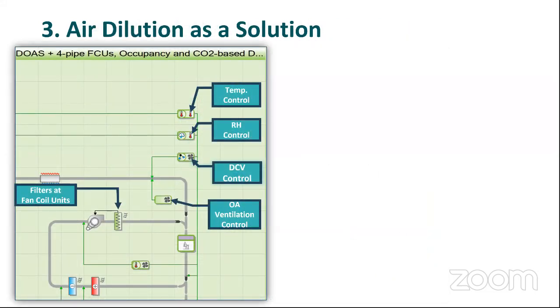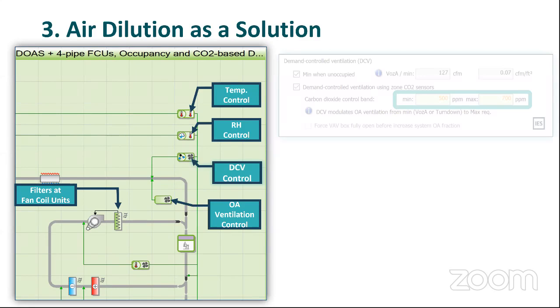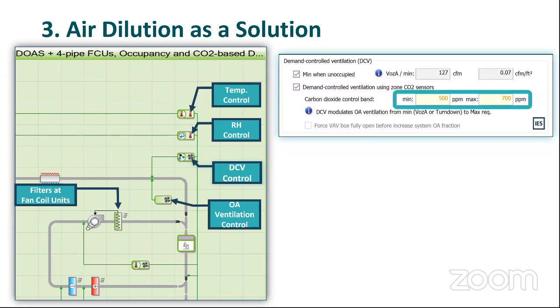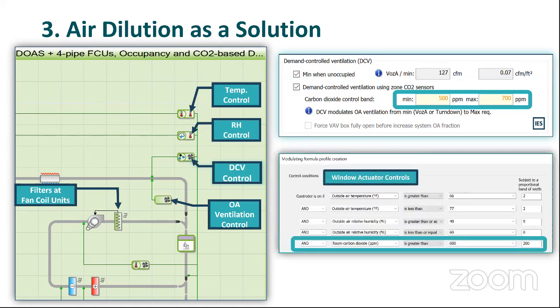Number three is air dilution. Air dilution can be by way of an airside economizer, natural ventilation, or in this case I'm showing a demand control ventilation controller. Some studies have shown that 600 parts per million of CO2 can be recommended as a proxy in some transportation buildings to mitigate the effect of virus transmission. In addition to the demand control ventilation, we can also apply those same controls with parameters to window actuators or natural ventilation.